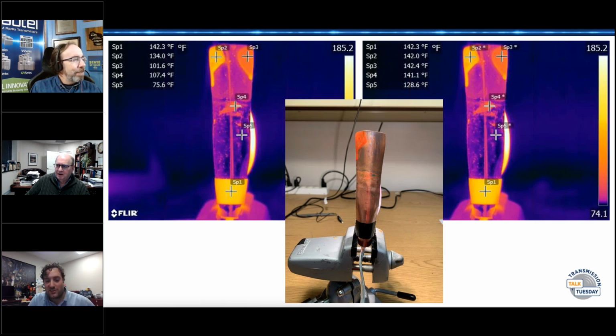Of course. So this is the perfect example of how radiation, or the way cameras see radiation, can completely trick you and give you false information. That's where having the certificate or the experience can help you avoid these mistakes. On this piece of shiny, polished copper, I put electrical tape at the very bottom, SP1, and that's my reference temperature. I know the emissivity value of that, so I know how much radiation that piece of plastic emits, and I can calibrate the camera based on that.